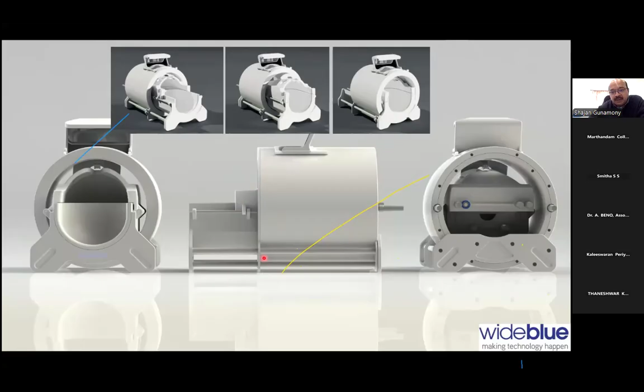So here is data from the University of Minnesota. Our coil is currently called the NeuroCam 70 coil, and these are the two NOVA coils. We see the comparison between the NOVA and our coil. Because it has 64 channels, there's so much more signal in the periphery, and we perform quite comparably in the center. So here you see the ratio between our NeuroCam and the NOVA coil. We have about 40 to 50% more SNR in the periphery, and we get similar performance in the center.